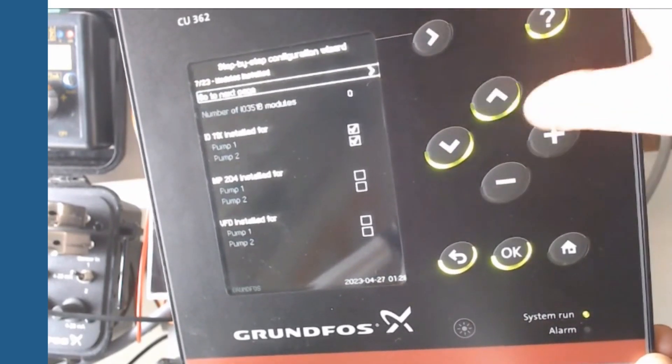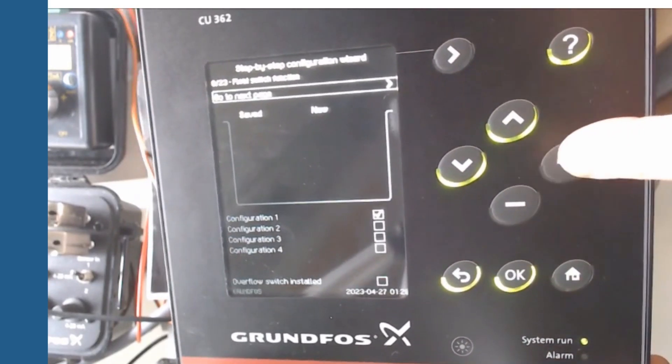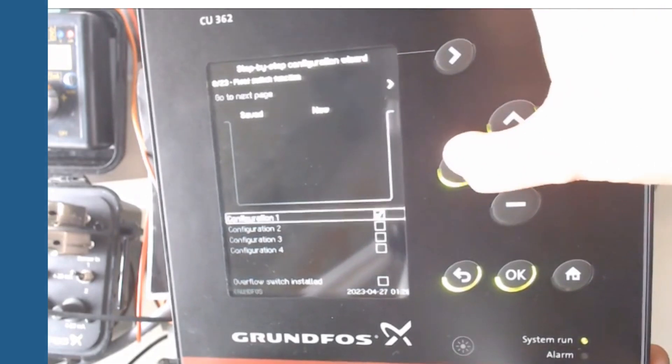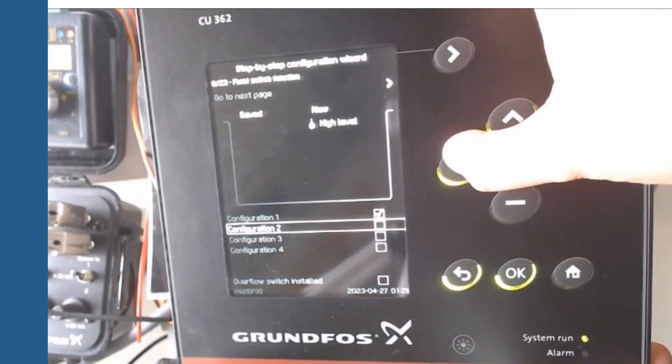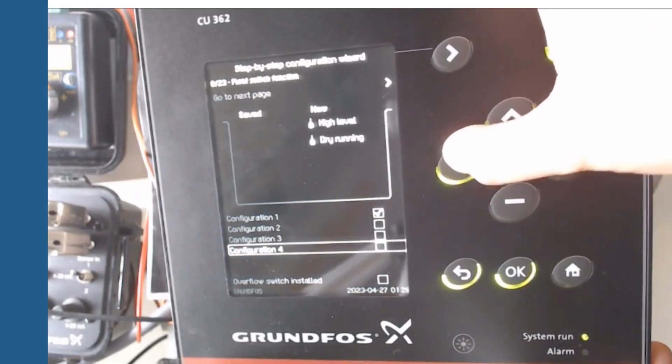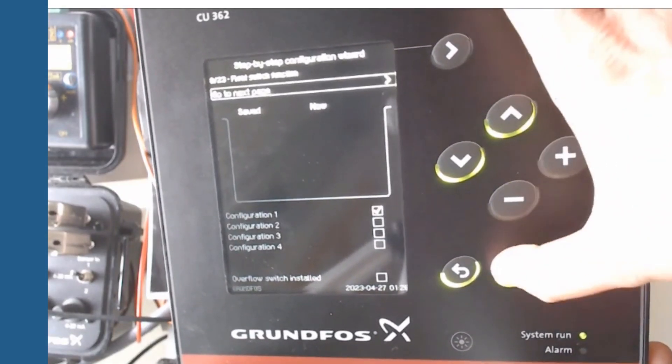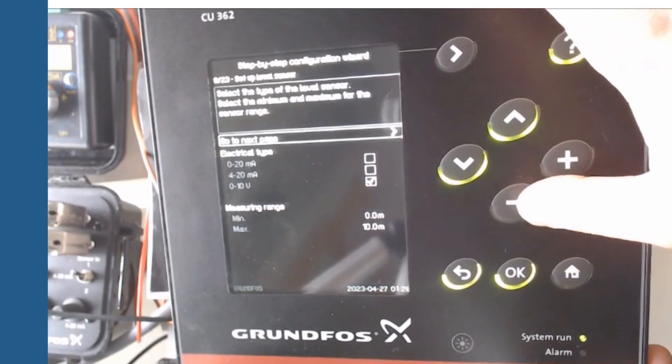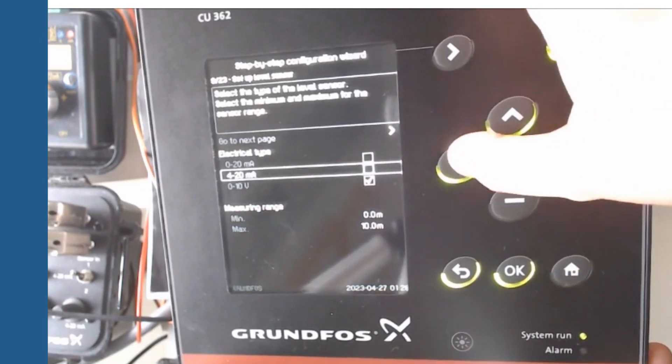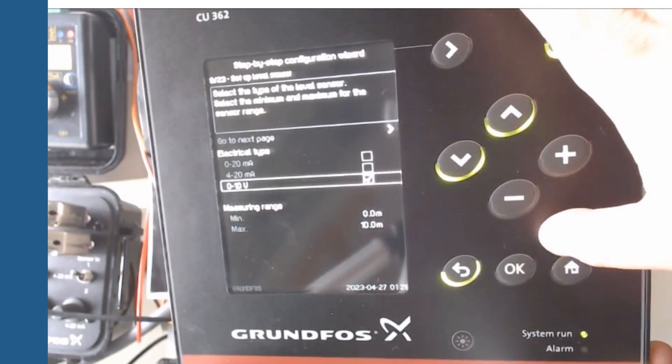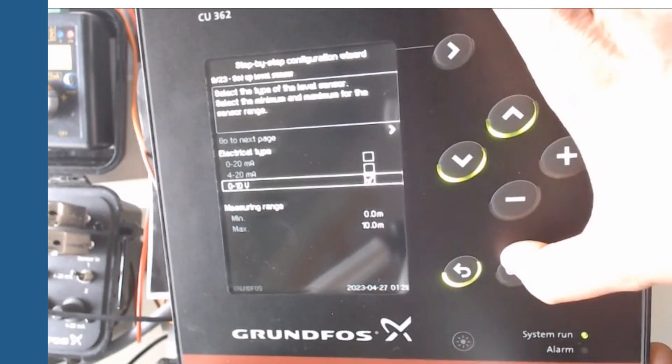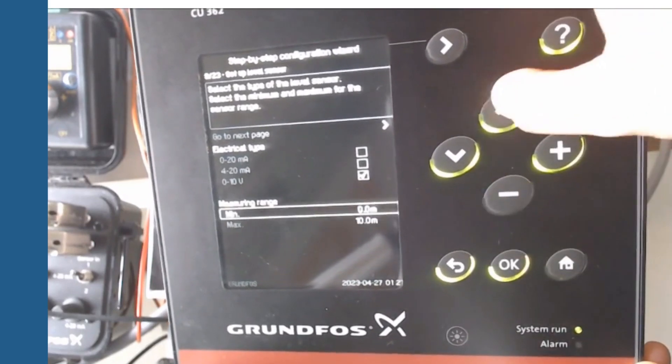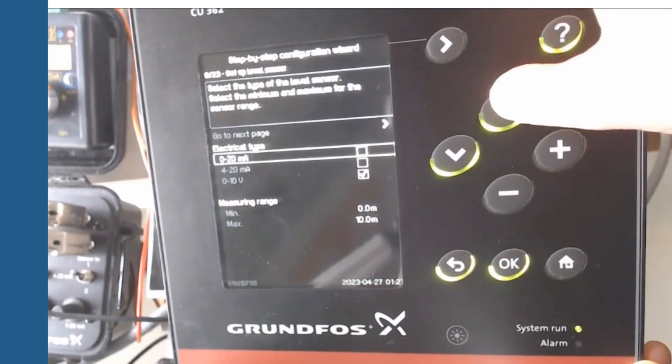If we have more modules in our panel we must set those here. In the next screen we should define the type of configuration regarding level switches in pit. In our example we set the configuration 1. After it we will set the electrical type of level control sensor. We select 0-10 volts and set the sensor range.